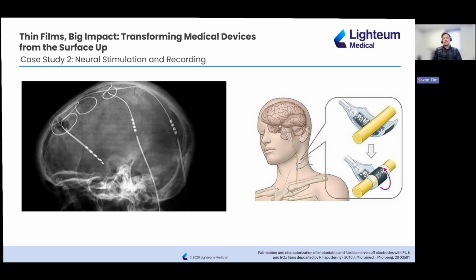But here's the problem. When you make an electrode physically small, its electrical impedance shoots up. High impedance means more noise and worse signal quality, which is exactly the opposite of what we need. So this is where thin film coatings become essential. By coating the metal electrode with materials like titanium nitride, iridium oxide, or PEDOT, we create a surface with enormous effective surface area at the microscopic level, while keeping the electrode geometrically tiny. That means we can keep the electrode small enough to listen to small groups of neurons, while giving it the electrical performance of a much larger electrode. So in other words, the coating allows us to decouple geometric size from electrical performance, which dramatically improves the signal to noise ratio for neural recording.